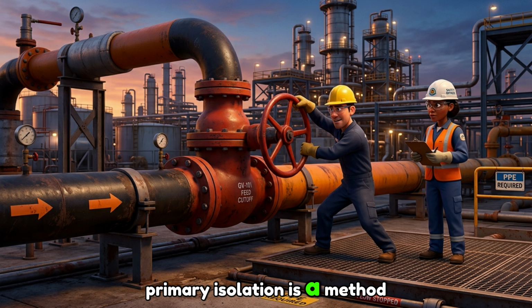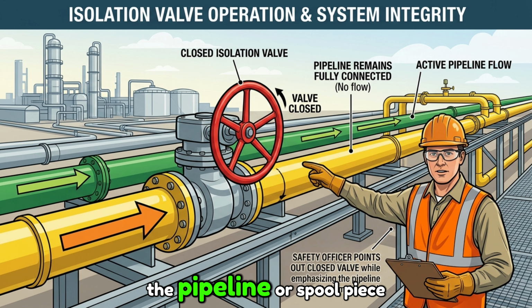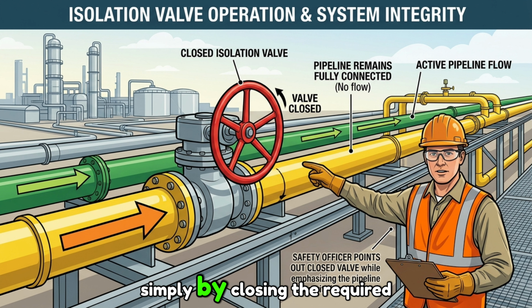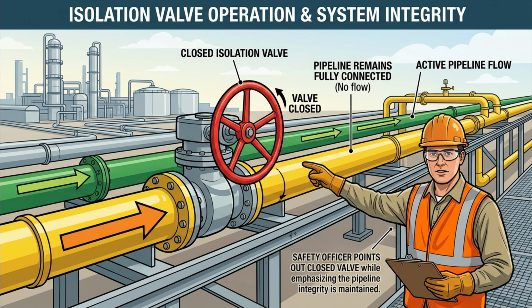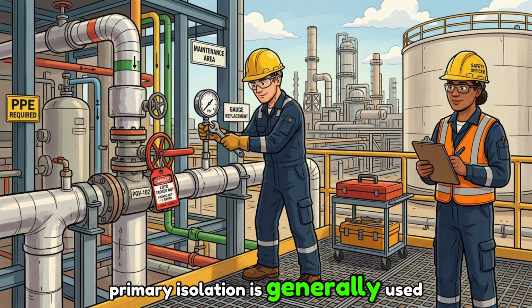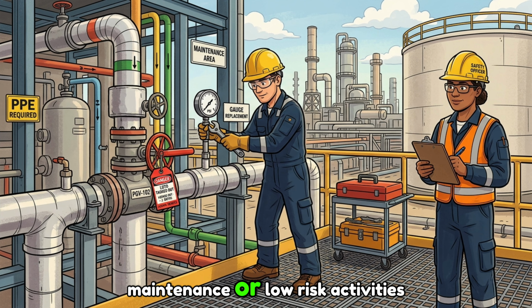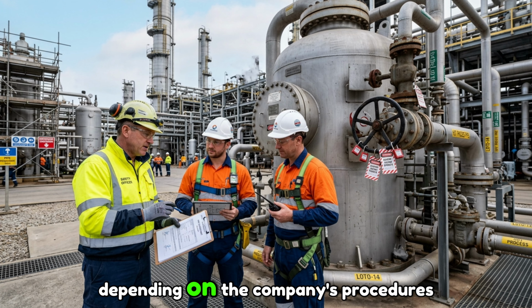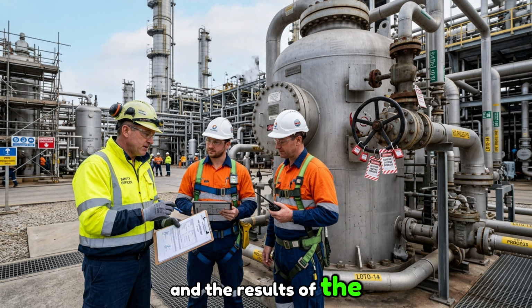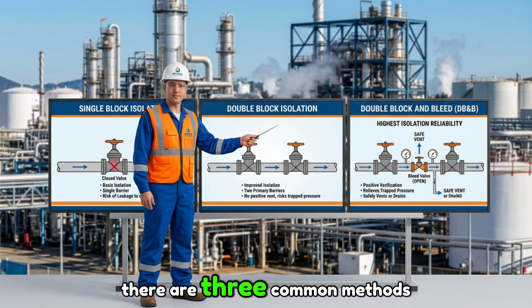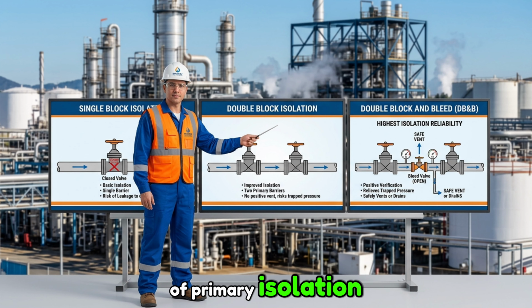Primary isolation is a method where process flow is stopped by operating isolation valves. In this method, the pipeline or spool piece is not physically removed. The equipment is isolated from the process simply by closing the required valves. Primary isolation is generally used for routine maintenance or low-risk activities, depending on the company's procedures and the results of the risk assessment. There are three common methods of primary isolation.